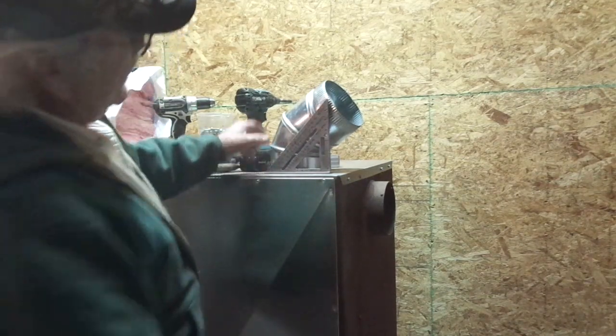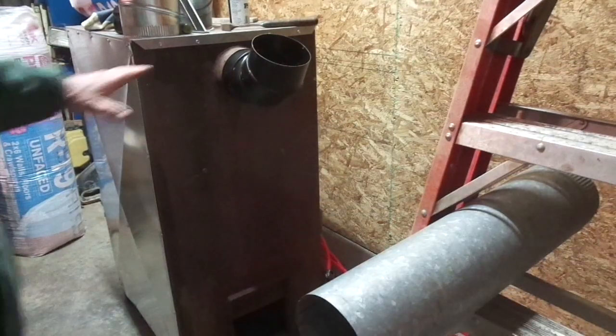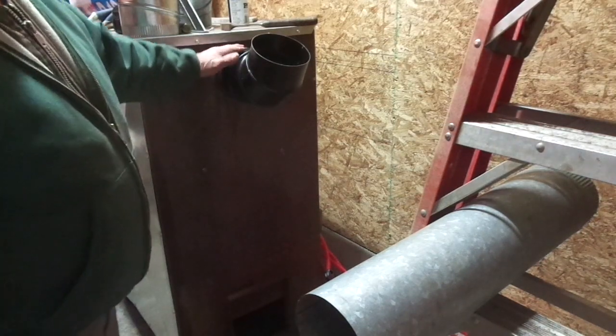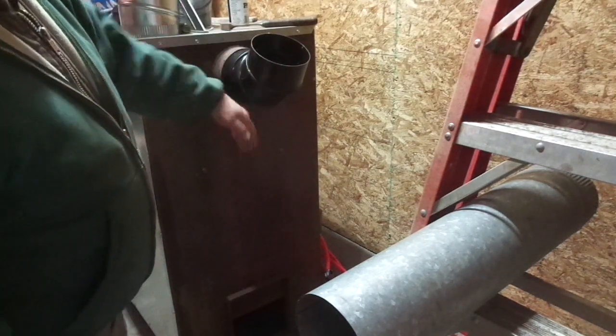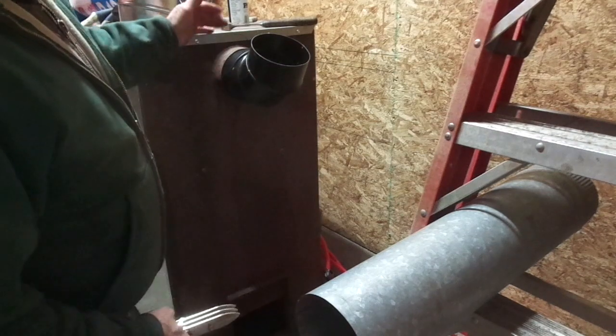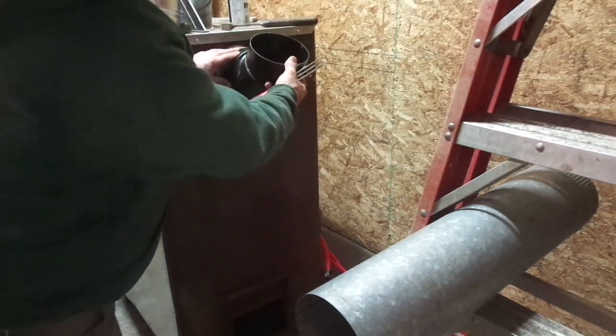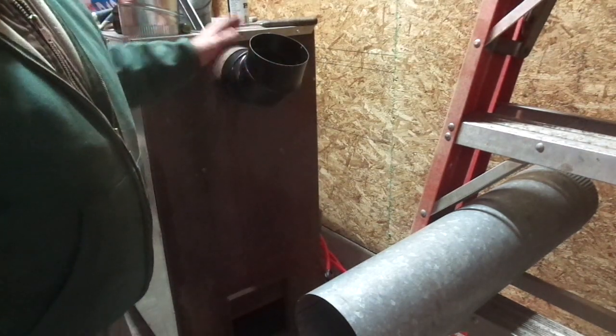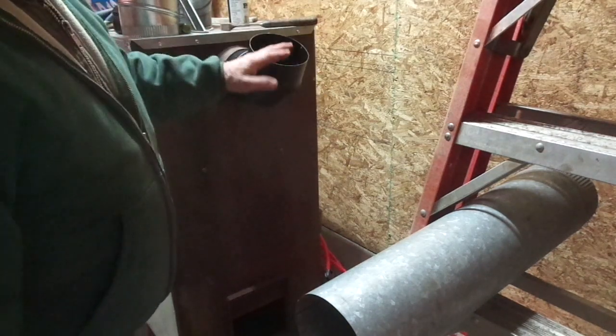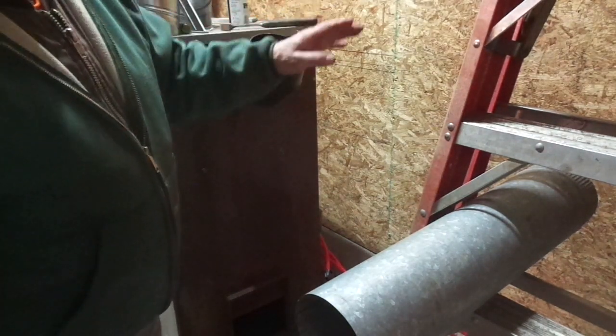It's roughly 45 degrees. Now remember how I said some furnace manufacturers suggest you run the flue pipe upside down compared to a forced air? This one here, I'm going to start off with it that direction, but I'm going to change midstream and reverse it, going inside the joints.